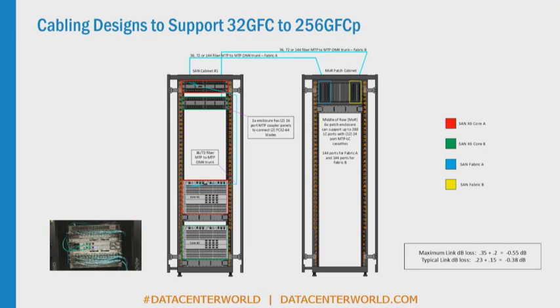Then you're taking this trunking going out wherever it's going, whether you're doing a middle-of-row patching, end-of-row, a zone cabinet, whatever. We're planning here for all these ports, 72 ports Fabric A, 72 Fabric B, but also we have room for double the growth. So I would plan for growth. We've seen a lot of applications where customers buy a switch, run connectivity to it and patch panels, and then need more ports. So you don't have to buy the cassettes or the MTP coupler panels, but at least have rack unit space or enclosure big enough for growth, and typically double is fine. That's one thing good about structured cabling, it's modular, you can buy it as you need it.